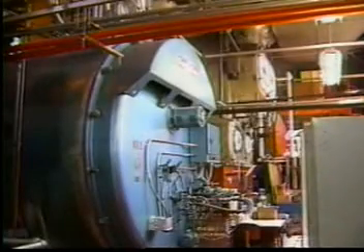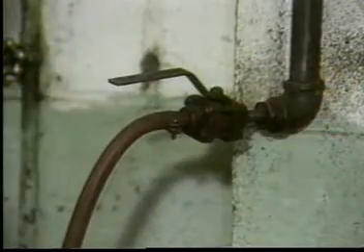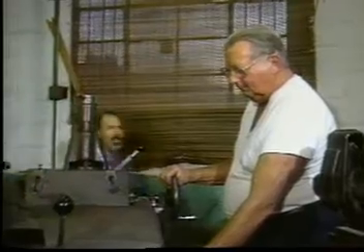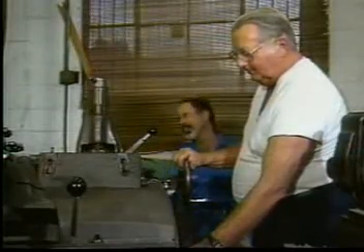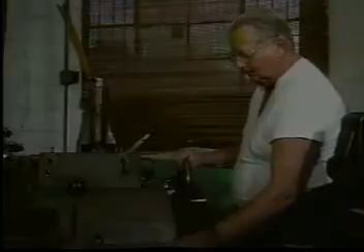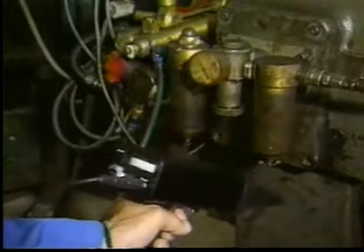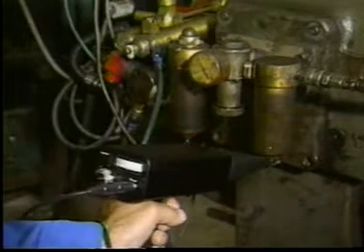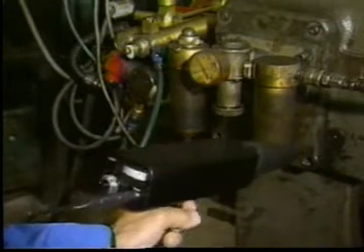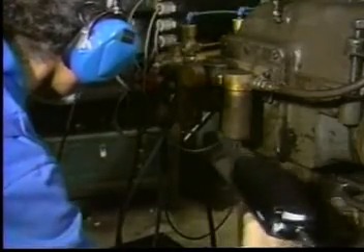Now let's discuss some techniques for detecting leaks in a noisy environment. When possible, it is best to turn off the source of competing ultrasound. However, it is often difficult or impractical to turn off competing sounds. In these situations, various shielding techniques can be used effectively to block out competing signals. First, try the rubber probe to deflect the unwanted sound. Changing the angle of the ultraprobe may also help.